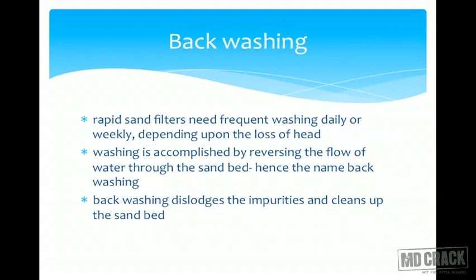The last step is backwashing — the cleaning of the rapid sand filter. Rapid sand filters need frequent washing, daily or weekly, depending upon the loss of head. Compare this to slow sand filters, which required cleaning once every few months and more or less operated on their own. With the rapid sand filter, operation and cleaning must be done almost daily or weekly — it is essentially a daily exercise.